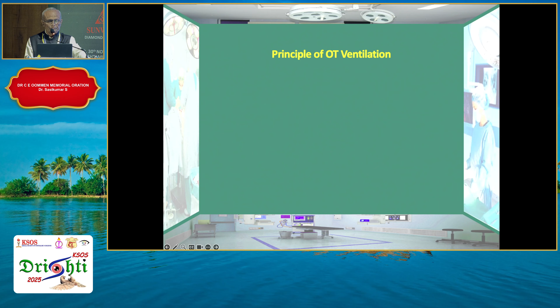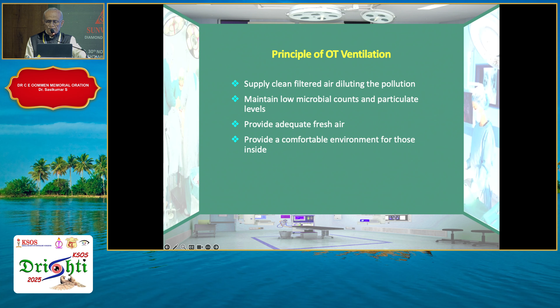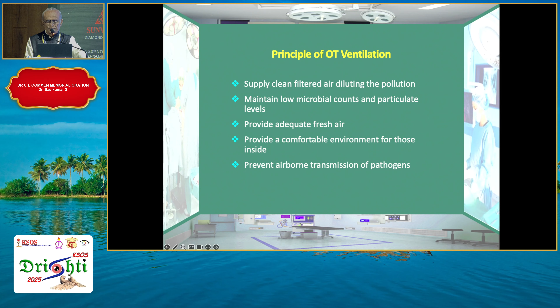What is the clean room concept in critical areas? The principles of OT ventilation are to dilute the pollution inside the room, keep the particulate count low, provide fresh air, make the room comfortable for the inmates, and provide an aseptic environment. All these have to be satisfied, especially in a critical area like an operation theater or ICU. To achieve these objectives, the supplied air is filtered to dilute the pollution, and to dilute the contaminated air, you add more fresh air.